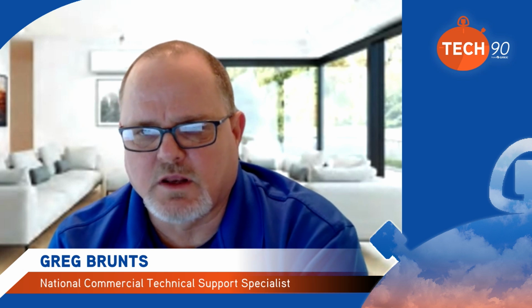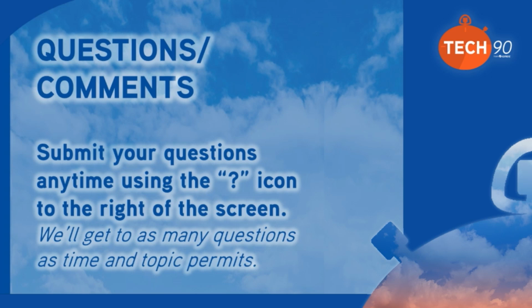But the thing I like about that tool is it's more versatile. I can use it on single zone, I can use it on multi-zone, and I can also use it to simulate an indoor unit or simulate an outdoor unit to help a guy troubleshoot for an E6 error code, which is one of the most common calls we get. And having that service tool just makes it really simple to troubleshoot a communication error.